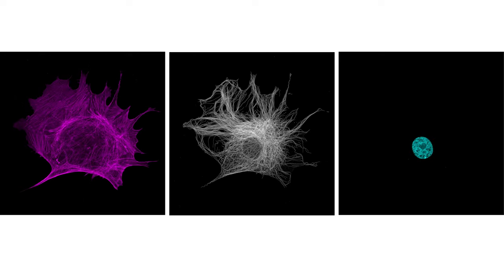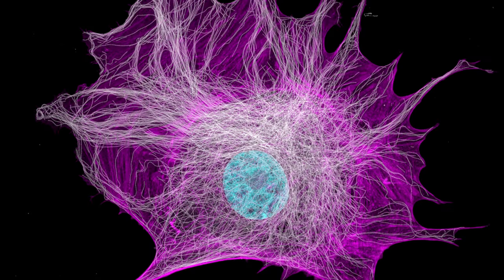Once our 2D image is built, this data has no color information, and corresponds to a single fluorophore only. If your experiments require imaging more than one fluorophore, you will need to scan an image for each fluorophore in your specimen. For a three-color fluorescence image, three separate image acquisition events are required. It is important that the image data from the individual fluorophore be kept separate for analysis purposes later on.